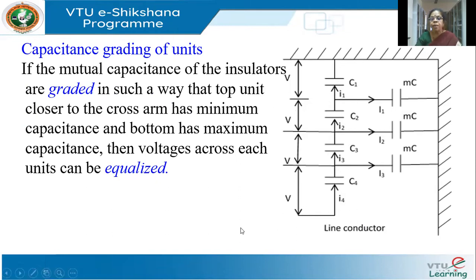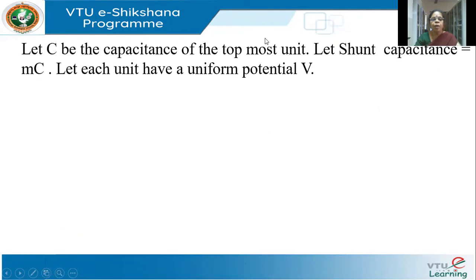The voltage is equalized across all units, so these are called equalizing capacitors. We want the voltage across C1 to be V, across C2 to be V, across C3 to be V — all of them equal to V. We will use the same method followed earlier, that is by writing KCL at different nodes. Let C be the capacitance of the topmost unit C1, let the shunt capacitance be MC, and let each unit have a uniform potential V.